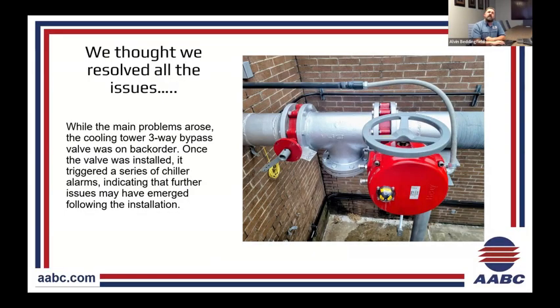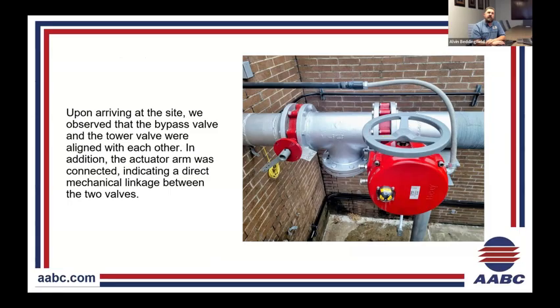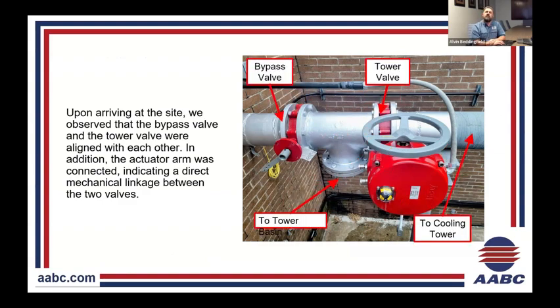So when we got there, obviously, the bypass valve was finally installed. Well, upon arriving, we realized that the valves were aligned with one another. The actuator arm was connected directly between them. So taking a spot, obviously, the left side is what's coming back from the building. Then we have the tower valve to the top right. The bottom one actually goes to the basin. They mechanically disconnected it for the time being, to help troubleshoot the issue. And then I guess that to the right of the screen is going to the cooling tower. So that's going to the cooling tower and going to the top side of the cooling tower.